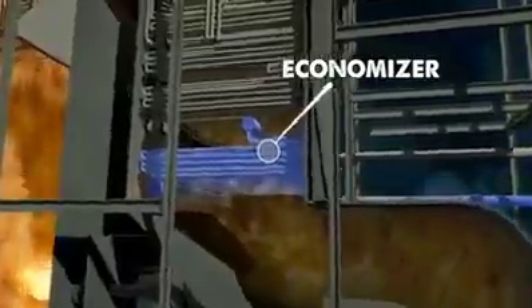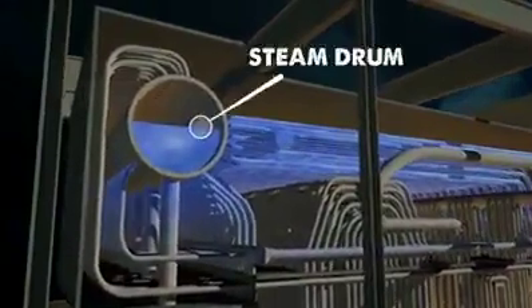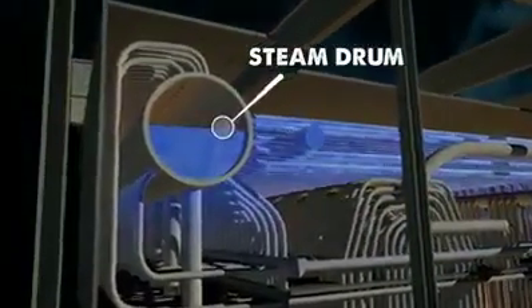Liquid water is pumped into the system at the economizer. Gradually, it's heated to base temperature before gathering at the steam drum, the system's main distribution hub for circulating water and steam through the boiler. Liquid water flows through large downcomers and into the base of the firebox. A network of 2-inch tubes line the firebox walls, and burners force feed a continuous supply of combustible fuel into the ultra-hot firebox. Eventually, the insides of the firebox burn so hot that its surrounding steel walls would melt if not for the tube-lined walls of liquid water.